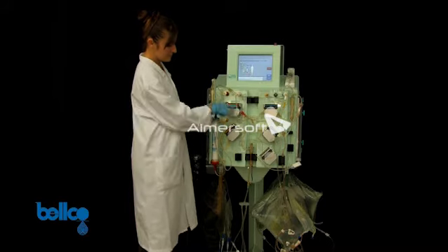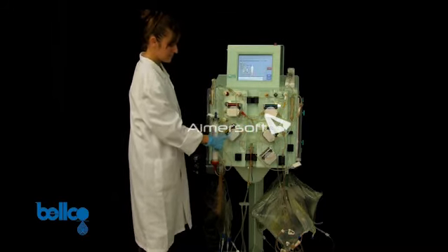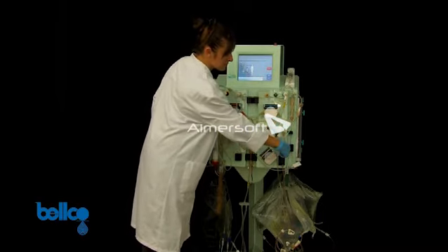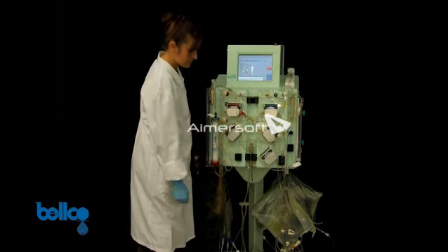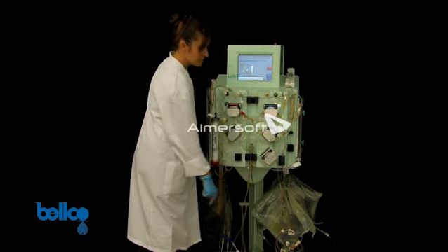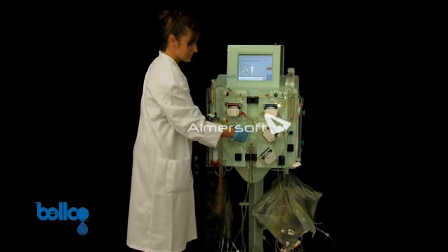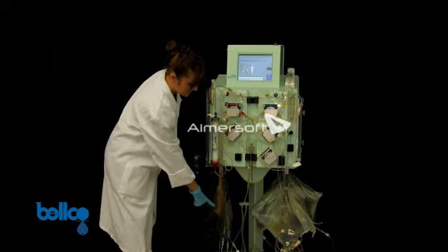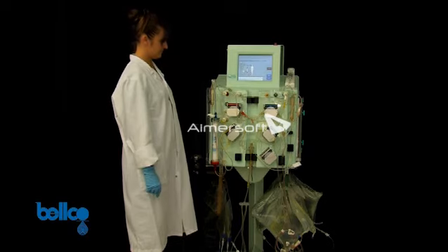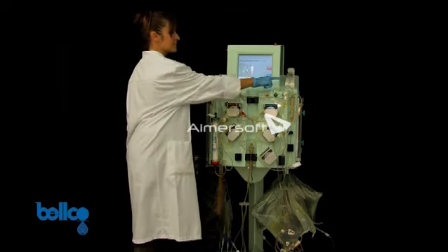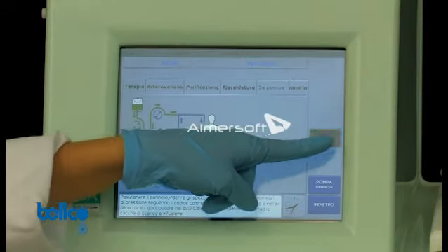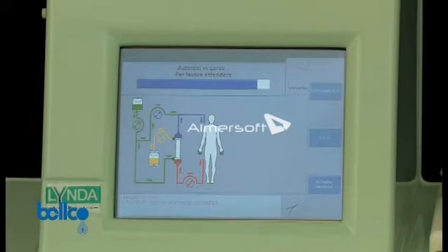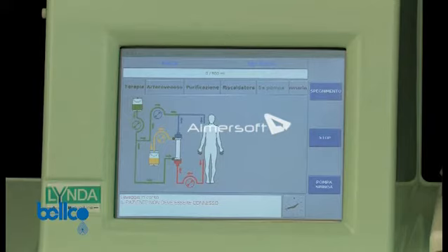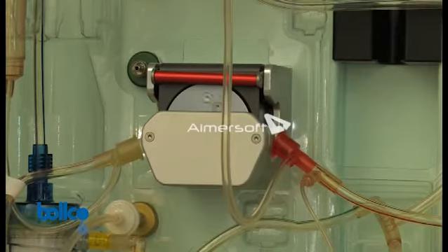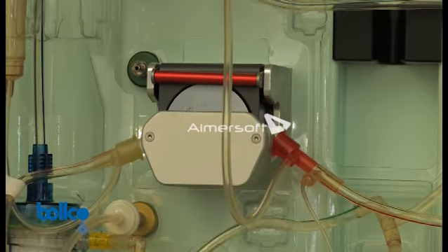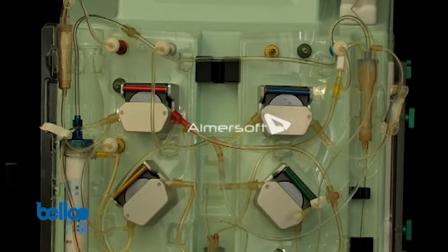In the final phase, check the device and the machine to make sure that all the components of the single-use device are well connected. Tap the Start button and start priming. During priming, the machine runs all the necessary tests to best prepare the device. In the CVVHD treatment, rinsing lasts about 10 minutes and the device is rinsed with 1.2 liters of infusion fluid.